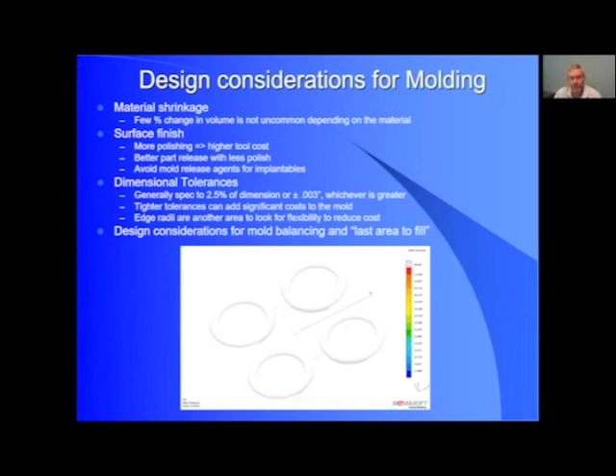So for dimensional tolerances, common design tolerances are 2.5% of dimension or 0.003 of an inch, whichever is greater. For a lot of drug components, we have to go much tighter in tolerances than that. Not uncommonly in the range of microns, because again, we're trying to design and fabricate a part where we're controlling the total drug load to much better than plus or minus 10%. Sharp edges are difficult to mold and can add costs and impact your tolerances. And so we prefer to make things that have slight curves to them to help things along.